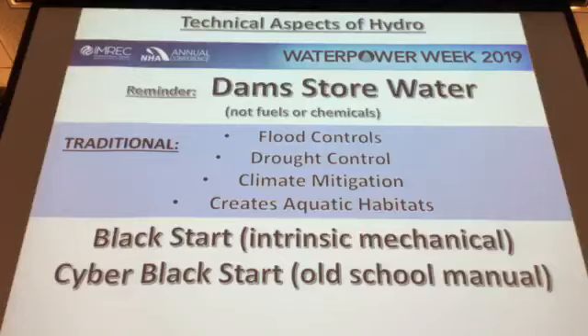And then down here, you're getting to the point where your losses, even though this might be 100 feet of elevation above your plant, you're still going to have a loss of efficiency because you're pumping all the way up, bringing it all the way back down. What you're going to gain, though, is a whole lot more water out of the watershed. Probably as much or more than Crater Lake put together. So, not something we've evaluated in any kind of detail, but there have been projects built like this, and it's pretty compelling because if your overall investment goes from $20 to $25 million, but now you're producing twice as much power and maybe half again or twice as much water, then you're just getting more return on your investment.